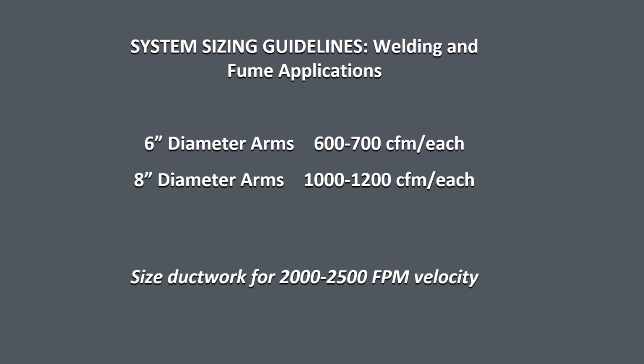Some simple sizing guidelines for welding and fume applications. For standard production type welding, we're going to use a 6-inch diameter arm at 600 to 700 CFM. But if we regularly weld on pre-lubed or oily material, it's going to generate a lot of smoke as it heats up. In that case, we may go to an 8-inch diameter arm using 1000 to 1200 CFM, so we can capture that larger exhaust cloud.